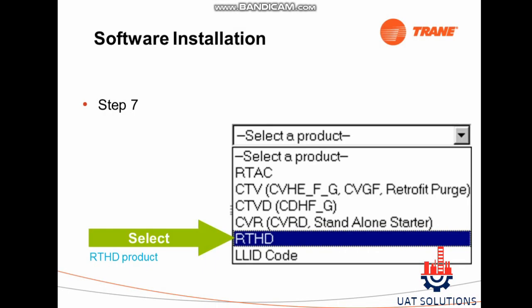Step 7: Now that all the required software are downloaded, let's start with the installation of TechView for RTHD chillers. Run the file TV7.02, select RTHD in the select product menu, and click Next.